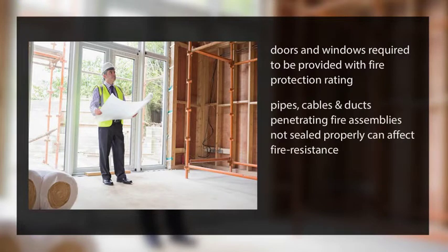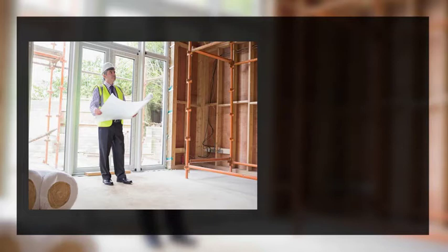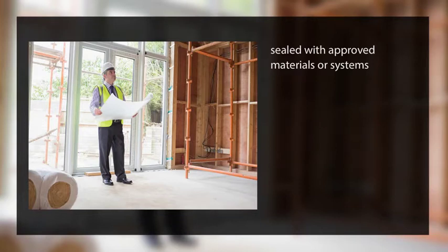Pipes, cables, and ducts penetrating the fire assemblies that are not sealed properly can also significantly affect the fire resistance rating of an assembly. These penetrations must be sealed with an approved material or system that resists fire and smoke from passing through these small gaps in the assembly.